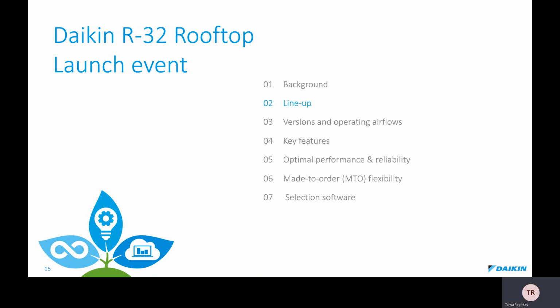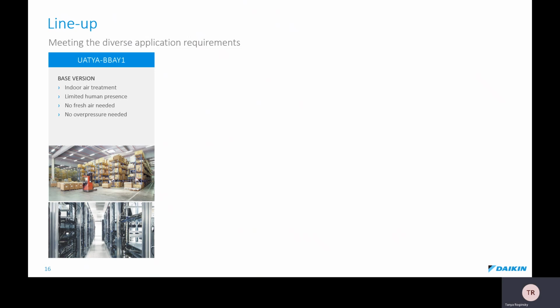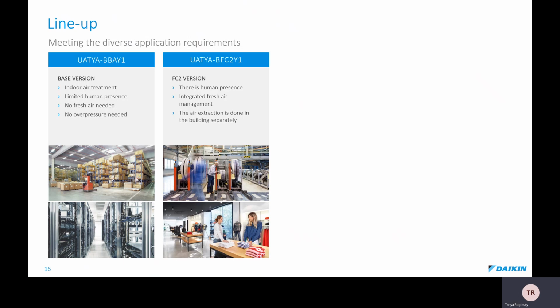And now let us have a look at the different versions of the new R32 range. First of all, we have the base series. These models operate on 100% recirculated air and are mostly used in warehouses, logistical centers, and technical cooling environments with limited human activity, so fresh air supply is not required. Secondly, we have the FC2 series, which has two damper versions with integrated fresh air supply. These units are suited for retail stores, larger malls, and manufacturing plants where there is human presence and fresh air supply is required. In this application, the building is overpressurized and pressure balance would have to be achieved by opening windows, doors, or by means of an extraction fan provided by others.